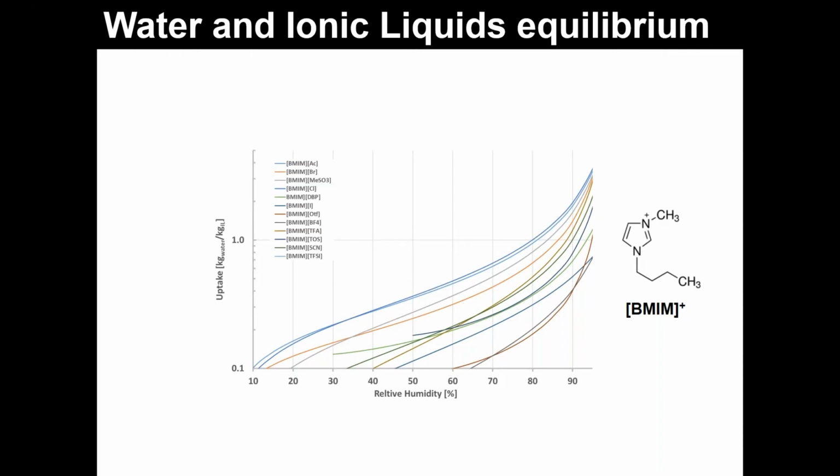Type 3 isotherms are often called unfavorable, but this is not a nice attribute for this type of isotherm, because we should remember that it is favorable or unfavorable depending on the specific application. And there are some applications working in the region of high relative humidity where these shapes of the isotherms are very welcome.